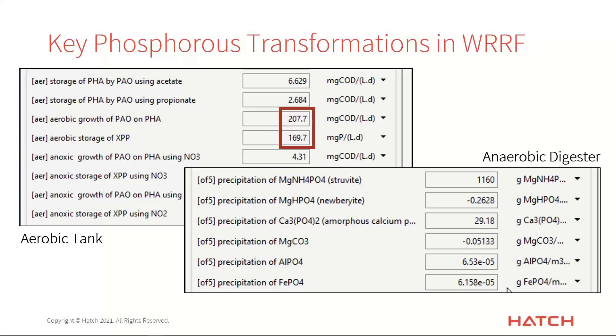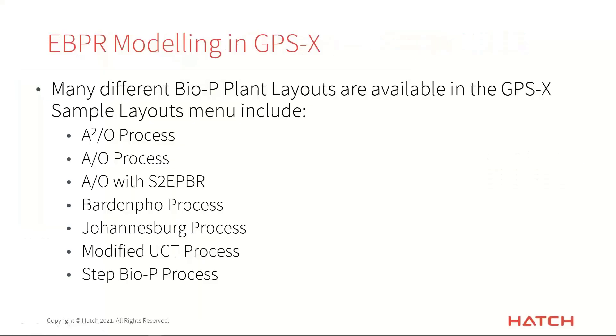As another example, here's the anaerobic digester. Right-click, go to Output Variables, Mantis 2 Rates menu, and you can see what is being precipitated in the digester. Most numbers are insignificant, except for the struvite precipitation rate, which is the big number. Those are handy tools for digging around and understanding what's going on in your system.